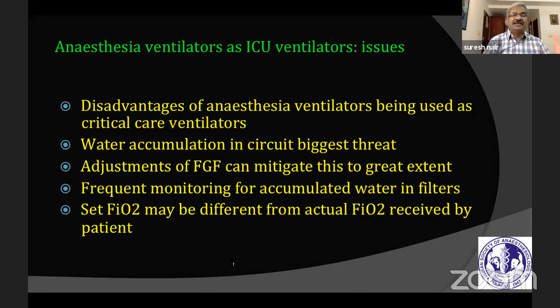The first problem is water accumulation. Water accumulation occurs because when you use closed circuits, you're using very low flows, 0.5 to 1 liter. This is possible only because the carbon dioxide absorber removes the carbon dioxide and we're able to maintain oxygenation.